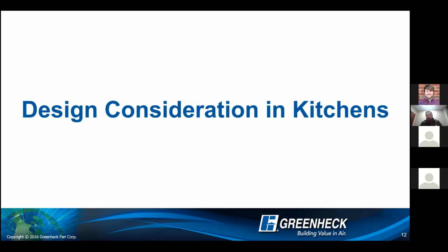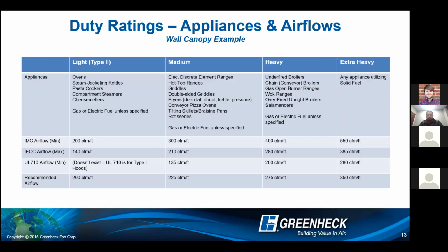Moving on to design considerations. So again, we're going to talk about design considerations and what all goes into designing a kitchen system. And just know that when Holden and their team are laying out the Greenheck product for you guys, this is what they're considering when they're doing their design. And they're supported by our KBS sales team with any questions for any designs that are a little bit outside the box. So first and foremost, I would contend that the design of a kitchen ventilation system is very easy. There are things you need to look out for, absolutely, but it's really driven by the CFM volume of the system. Once you know your exhaust volume CFM, the rest of the system really designs itself.